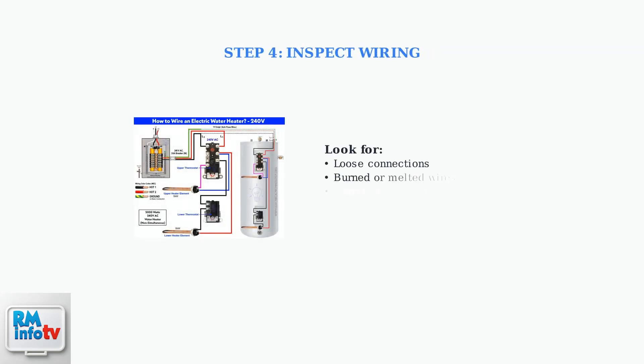Examine all wiring connections for damage, corrosion, or loose connections. Faulty wiring is a common cause of breaker trips and can be dangerous.